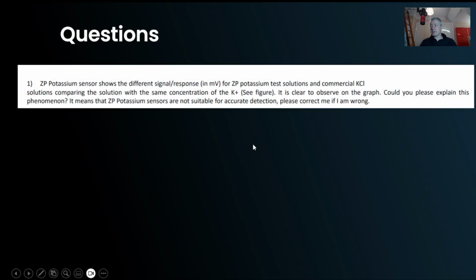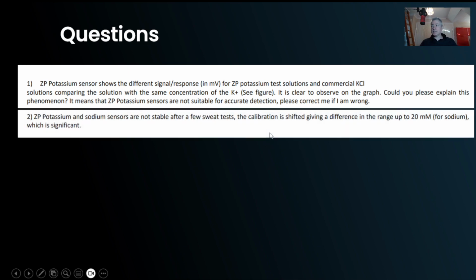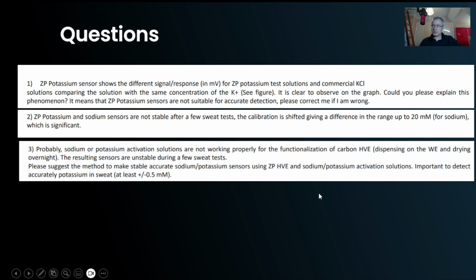The first question is, somebody's using two different solutions. They're getting response to potassium, but there's an offset difference between the two solutions, and I will address that today. Because I think the way they're testing the sensor by bringing solutions on and off, it's bringing a variability into the signal, which is a kind of offset variability. I don't think this is the way they're intending to use the sensor. But that offset variability is causing them concerns about essentially the accuracy of the sensor, and I'll address that.